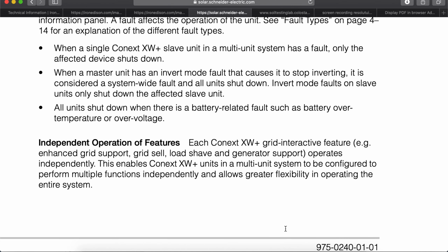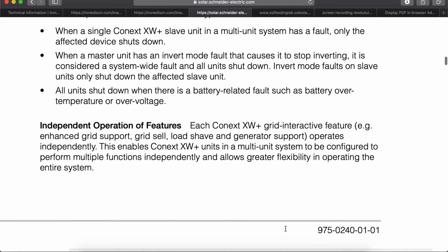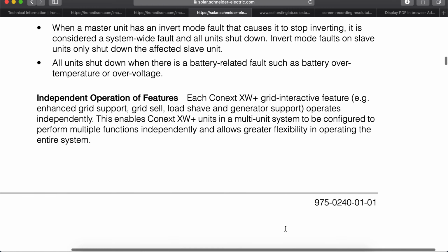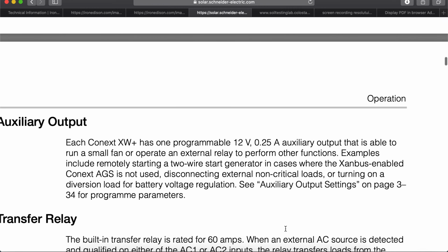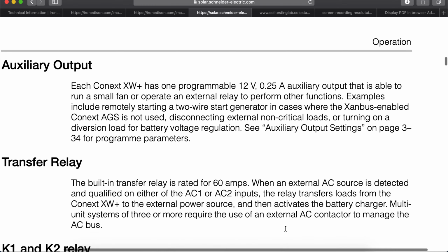Independent operation of features. Each Conext XW Plus inverter's grid interactive features, e.g. enhanced grid support, grid sell, load shave, and generator support, operate independently. This enables Conext XW Plus units in a multi-unit system to be configured to perform multiple functions independently and allows greater flexibility in operating the entire system. That's important to know. We're almost done for today.